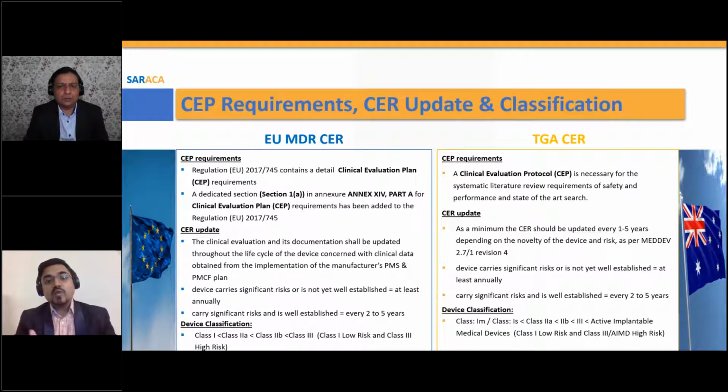When I say plan, there is a dedicated section, section 1A of Annex XIV Part A, that is completely for clinical evaluation plan requirements. All those requirements you need to address in the clinical evaluation plan. So nowadays, in the clinical evaluation plan, you need to address the device description and all the details of the packaging insert, like contraindications, warnings, cautions, precautions. Each thing you need to define inside the clinical evaluation plan.